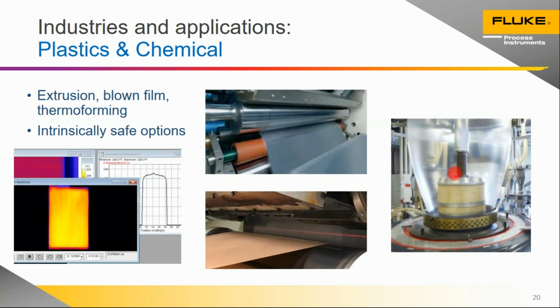Here you see plastic being vertically extruded as a blown film, and then it will be collapsed and turned into either paper bags or something like a Reynolds wrap or saran wrap or something like that. In many of these applications, you're using those 3.43 micron sensors so you do not see through or avoid transmitting through that thin material.